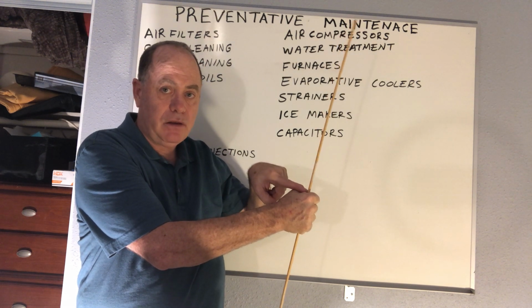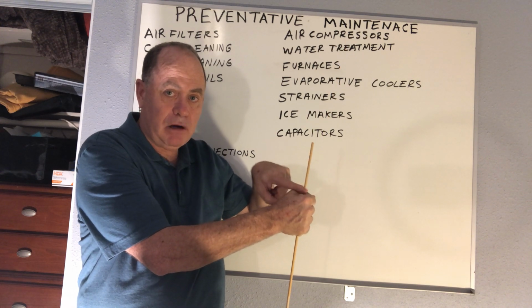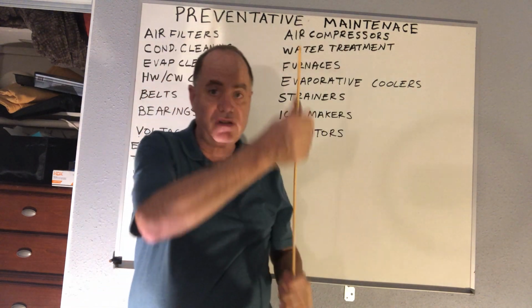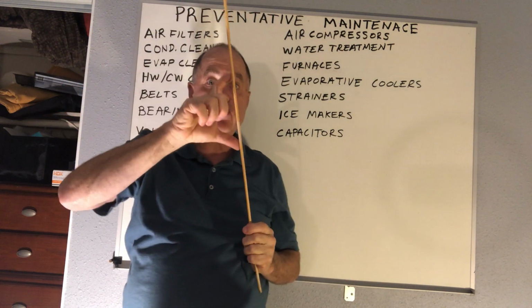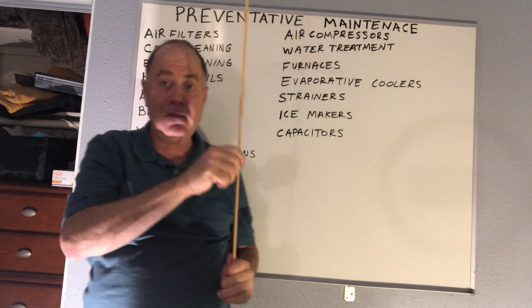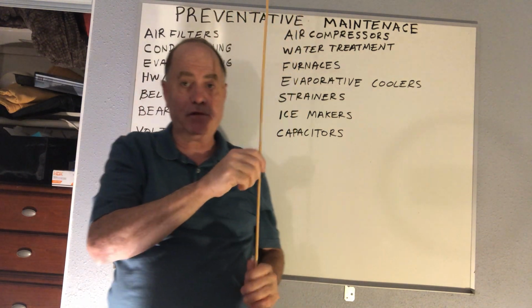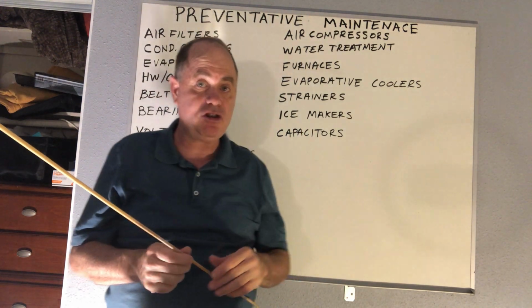And then the next month, you could put a line with the date on it, and then the next month, and you can see how much chemical you're using. And I have these sticks, almost look like tree rings, and it shows the tower running more and pumping more chemical in the summer. And then if you come the next time and do it after like 3 weeks or a month, and it hasn't pumped any chemical, you may have an issue.